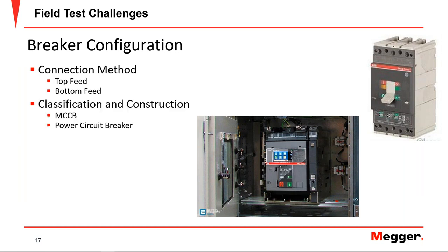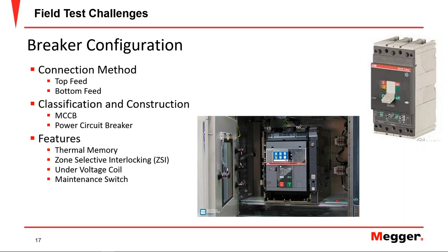The classification and construction, right? Is it a molded case? Is it a power circuit breaker? And the features that the circuit breaker might have, right? Especially with the power circuit breakers, if I have thermal memory, zone selective interlocking that I may have to disable with the elements provided by the manufacturer of the breaker.